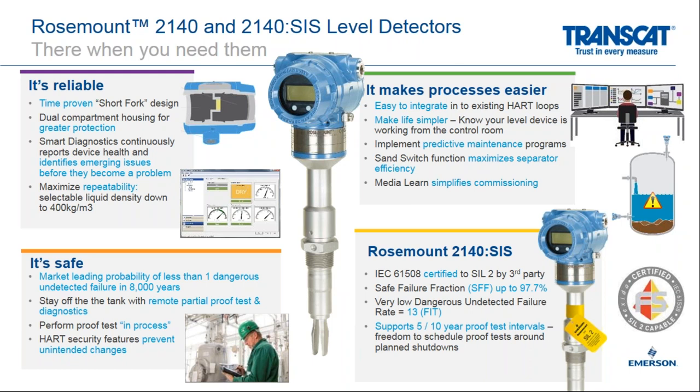Okay, next question. How many wires does the 2140 require, and do I need to pull new wires? That's another great question. We get this question a lot, Nicole. This device is operational on a loop power setup, so similar to what you would wire a pressure transmitter or a temperature transmitter.